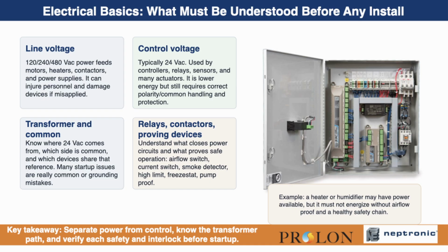If the transformer's secondary, common, or safety chain is open, the equipment may have power available and still not operate correctly. That is why the team must verify the transformer path, identify the common reference, and confirm each interlock and safety before startup. Many apparent control failures are really wiring, common, or safety chain problems.